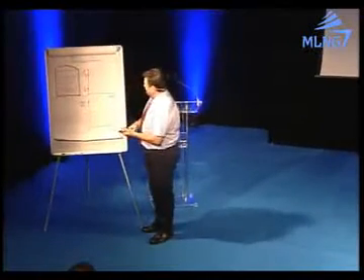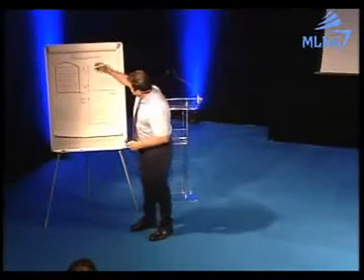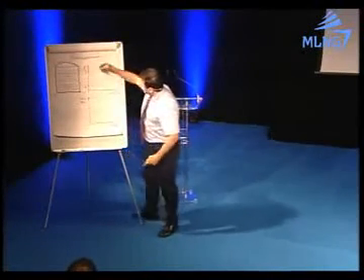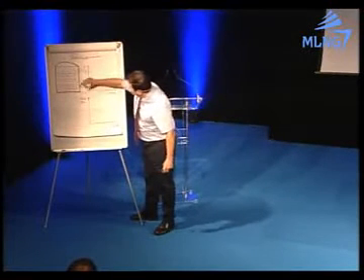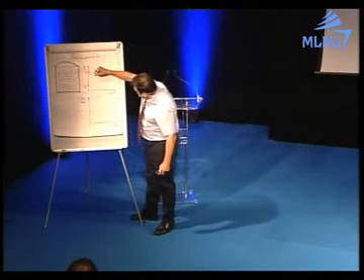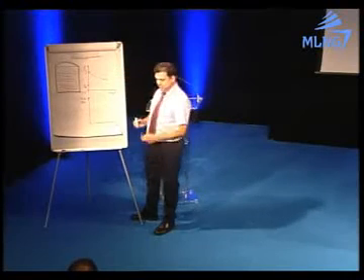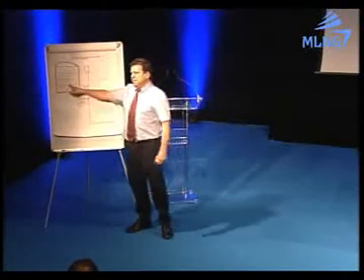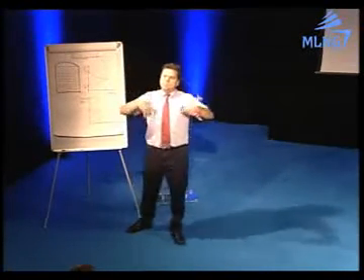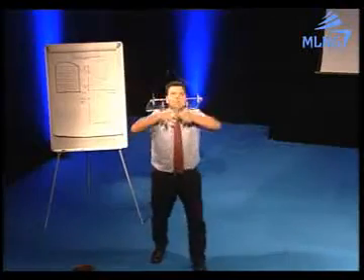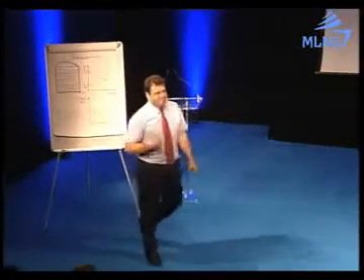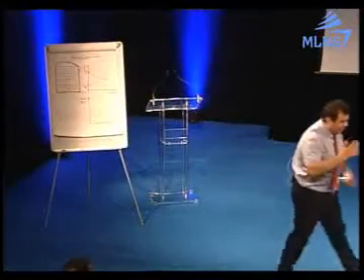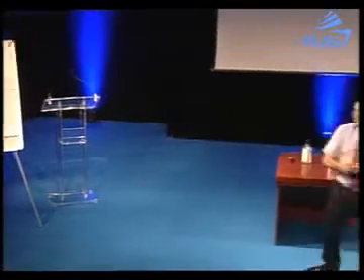So what happened with time? The density of the heavier LNG will be less and less with time, because it has more temperature, and with more temperature the density is less, like the balloon there. What happened with the upper layer? The upper layer is a normal boiling LNG. It's boiling.